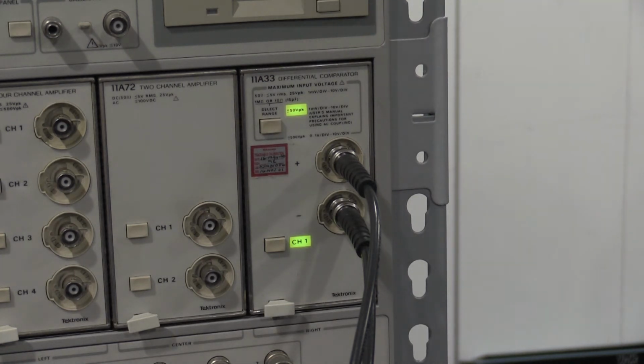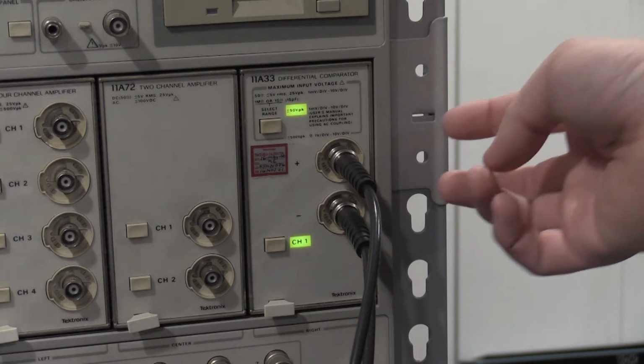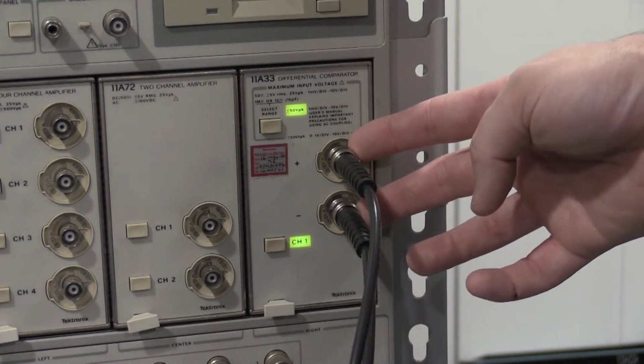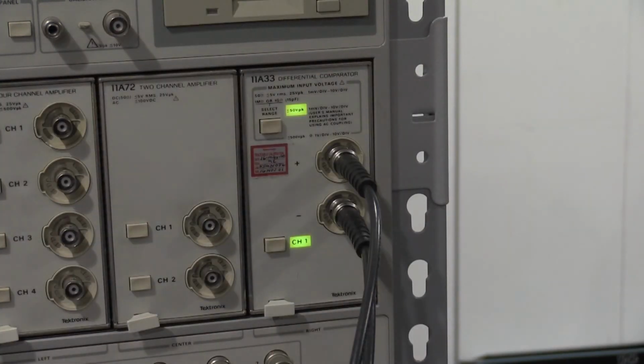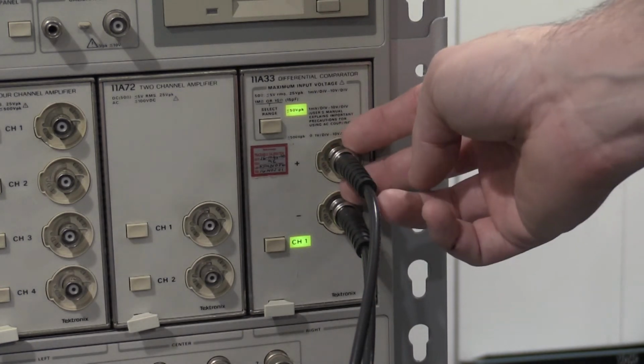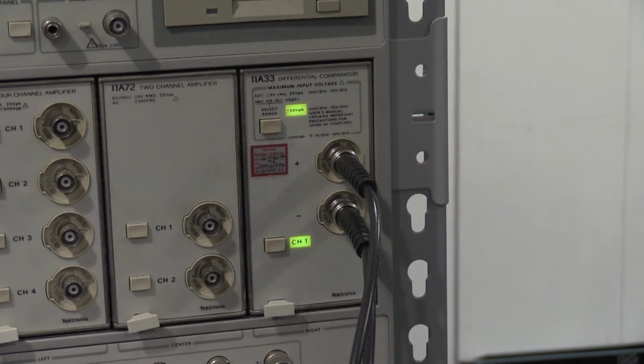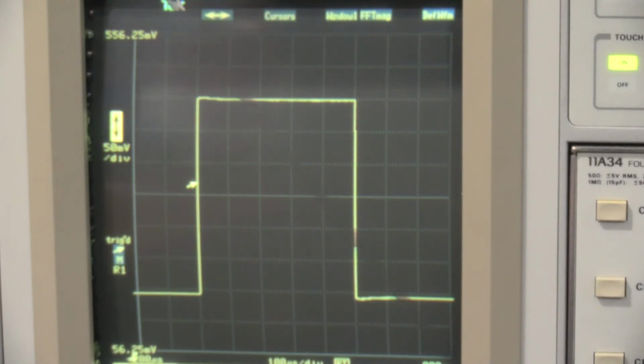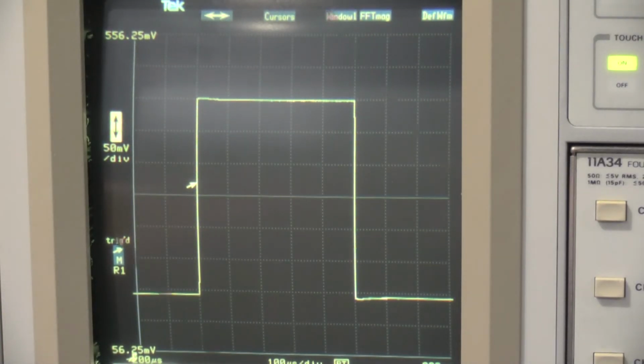Not necessary, but it's the best way to make this particular measurement during the calibration that I have in the lab. Also, the 11A33 can natively do 50 ohms. That's why there's no 50 ohm terminator. It is set to 50 ohms, so I have proper termination on the trigger lines. Here's our 6 divisions of display, and that looks very healthy. And that is with the signal standardizer installed.